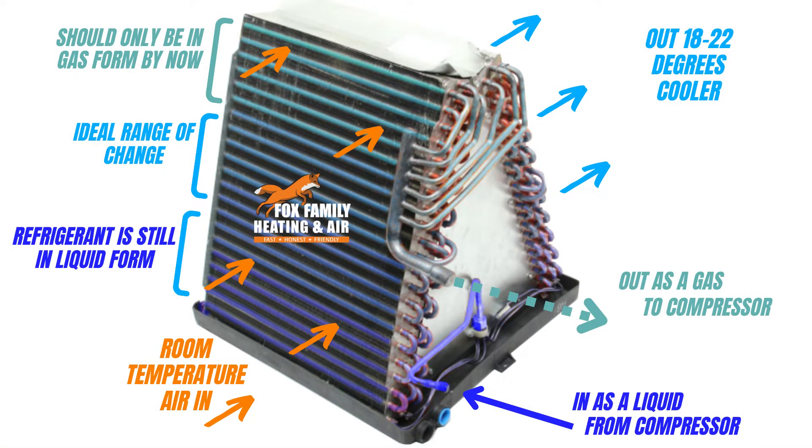What's happening inside the evap coil? Imagine looking at the inside of an evaporator coil while the blower air is going through it. With the right amount of refrigerant flowing through the TXV, you'll see enough liquid refrigerant in the coil, but not so much that it ends up leaving the coil in the suction line back to the compressor. It's a delicate balance. While the refrigerant goes through the TXV in liquid form, about halfway through it changes into a gas. And where that change happens means no more liquid refrigerant exists — it's gas now. And that point in the evaporator coil is the superheat measurement.